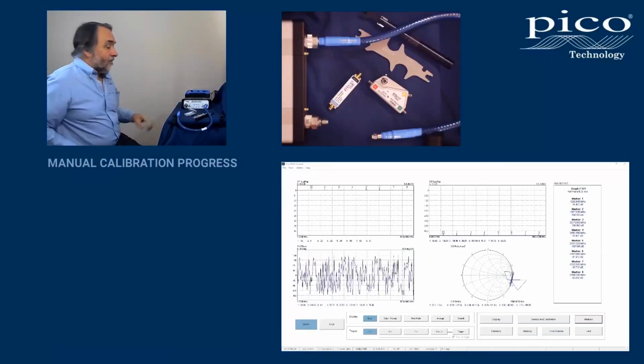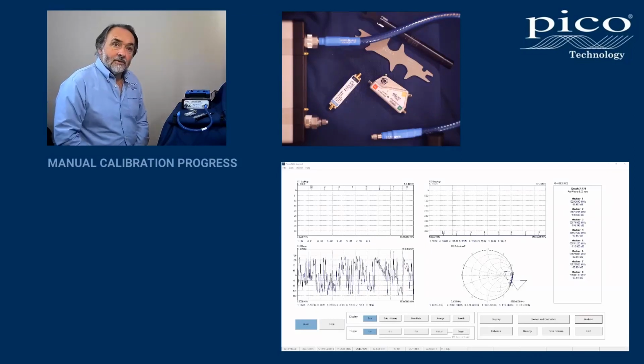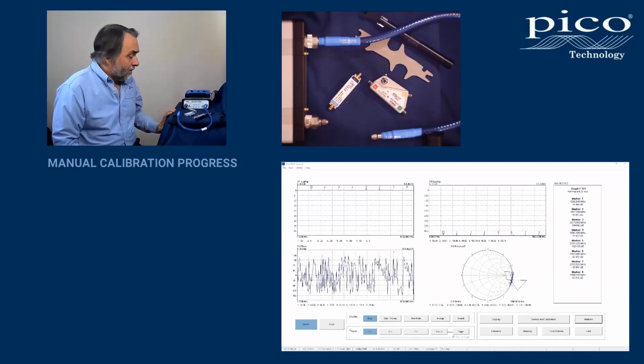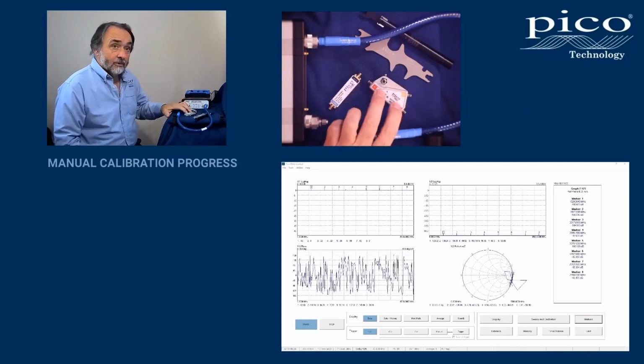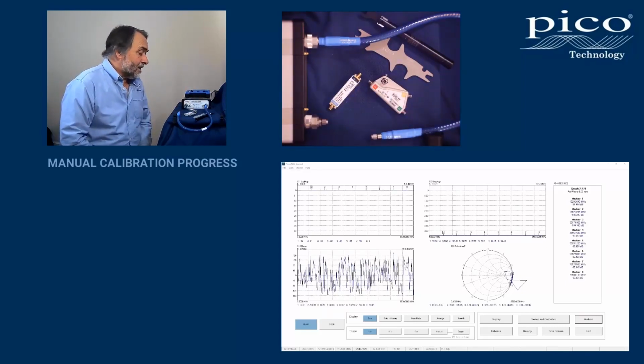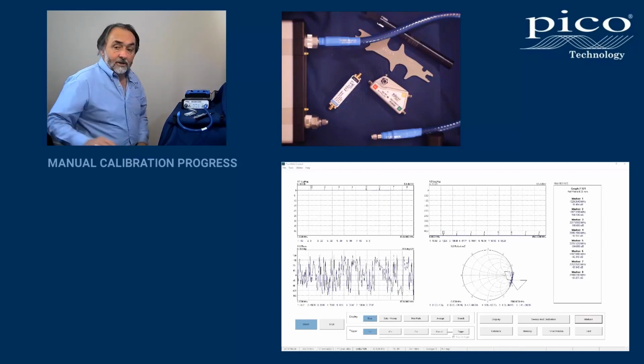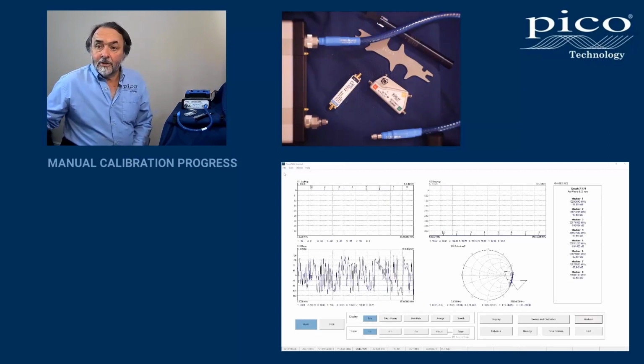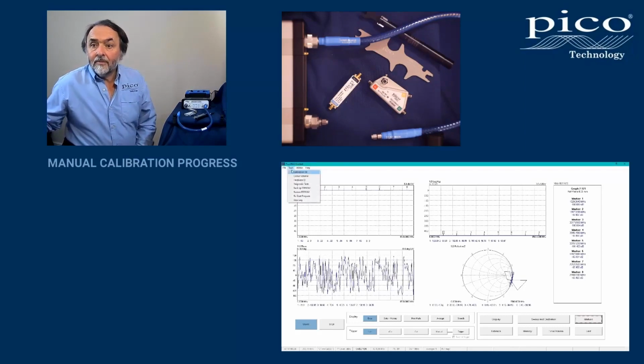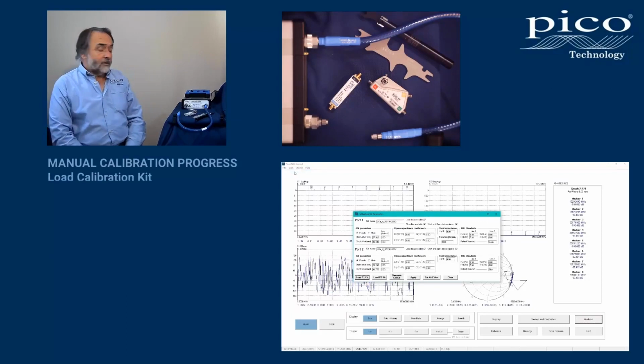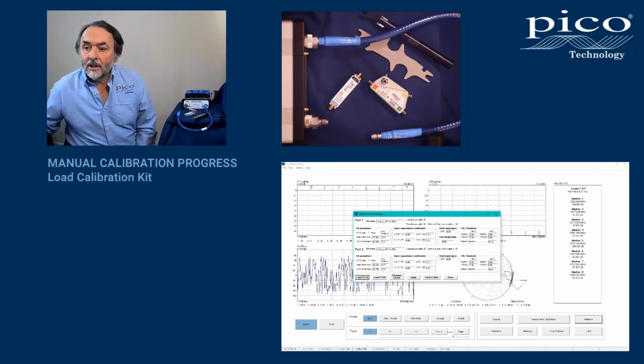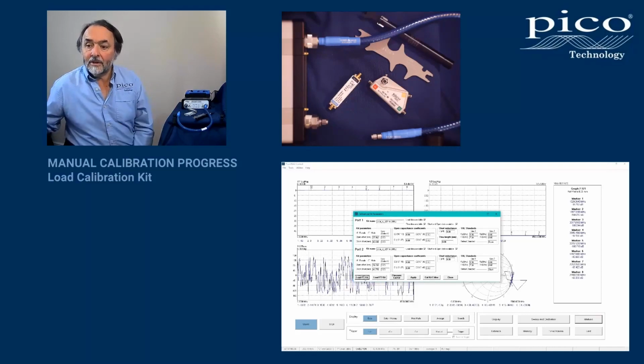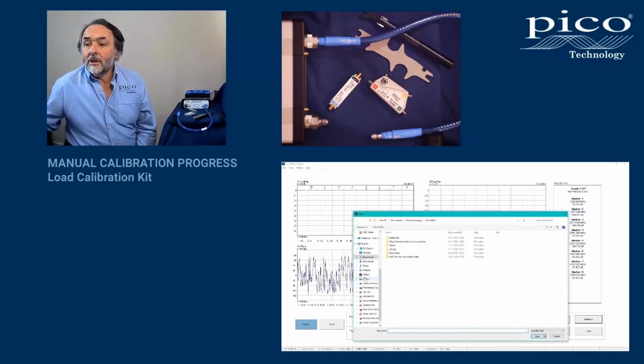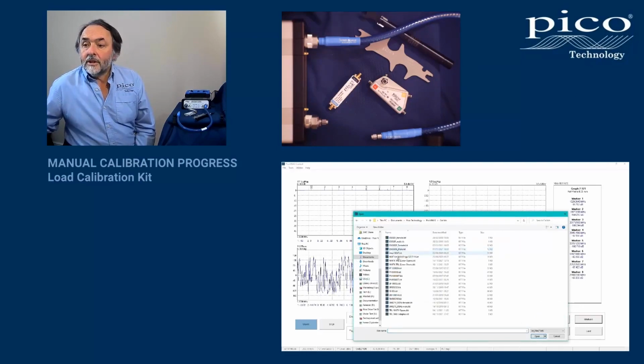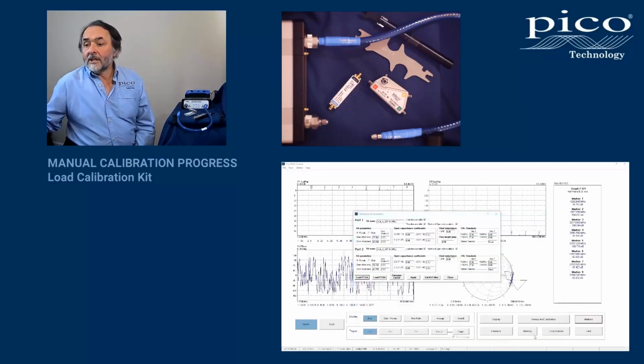You can see here I've got two male PC 3.5 ports that I wish to calibrate, and I've got one of our premium female calibration standards here. So let's get this underway. The first thing I have to do, of course, is to check which calibration kit I've got loaded to the VNA at the moment, and it's currently the eCal, so we want to do a manual cal, so we load kit 1, cal kits, and I'm using this one here, so let's load that.